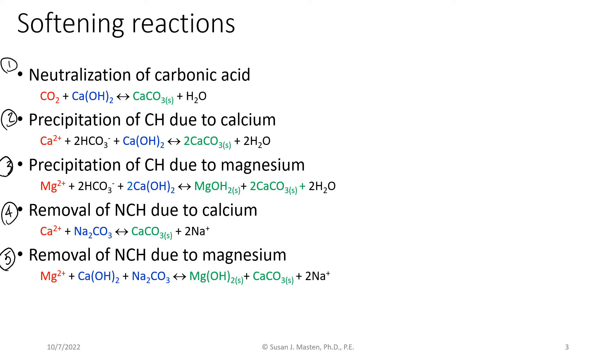Also need to think about, we said in the notes, that 40 milligrams per liter was our cutoff where magnesium became problematic. We're at 25 milligrams per liter. Both of those are as calcium carbonate. So think about, do you need to remove magnesium, or do we only need to worry about neutralizing the carbonic acid, precipitating the carbonate hardness due to calcium, and the non-carbonate hardness also due to calcium?